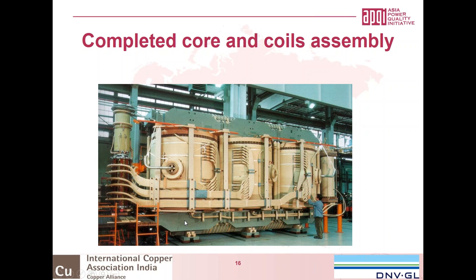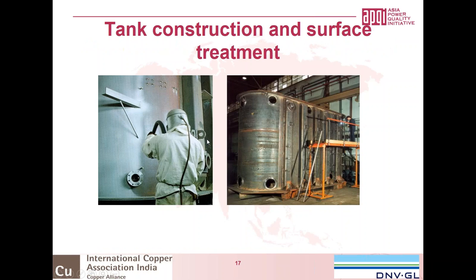So you'll see a lot of construction material within a transformer, and in this case it's made of iron. So you can imagine that in case you have an electrical field, it will also have some currents within those construction parts. The tank, I already told you, is also mainly made of iron or steel, and in some cases, for some transformers where you have bushings going on, they will use stainless steel because that's non-magnetic, so it will also reduce your losses in case you have very high currents.